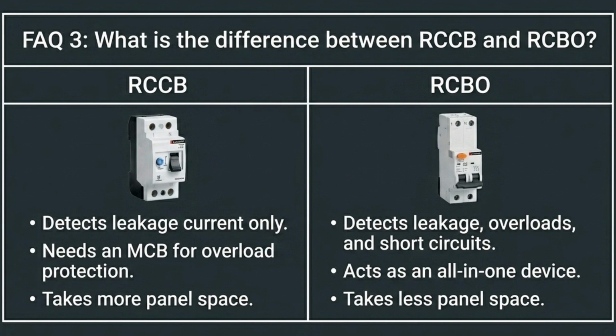FAQ 3. What is the difference between an RCCB and an RCBO? An RCCB detects leakage current only and needs a separate MCB for overload protection. An RCBO is an all-in-one device that detects leakage, overloads, and short circuits, saving panel space.